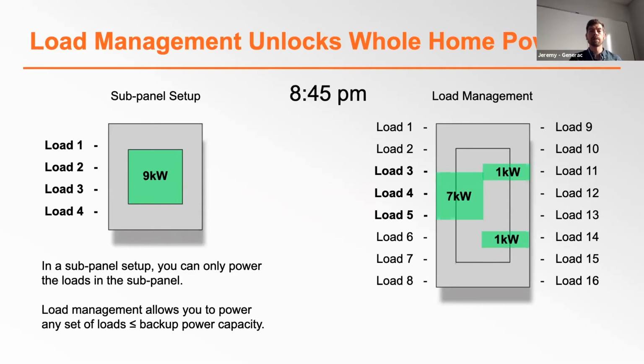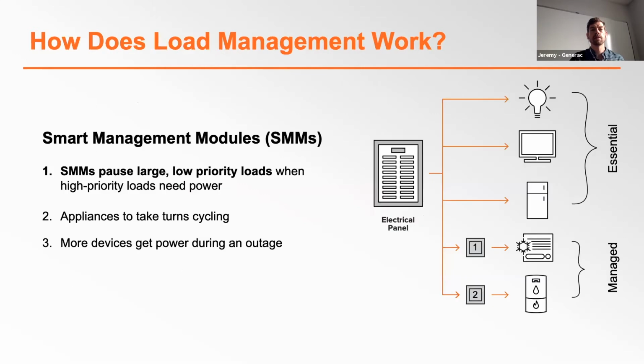And this is a major benefit of load management. Your customer will be able to operate within the normal range, just turning on the things that they always turn on, and they're going to have access to all their loads. And they'll do this safe in the knowledge that their system can't be overwhelmed by any combination of loads. Again, some loads might be unavailable to run simultaneously, but nothing is going to be unavailable altogether. This is a higher performance setup than a sub-panel system like this, where you just get these static loads.